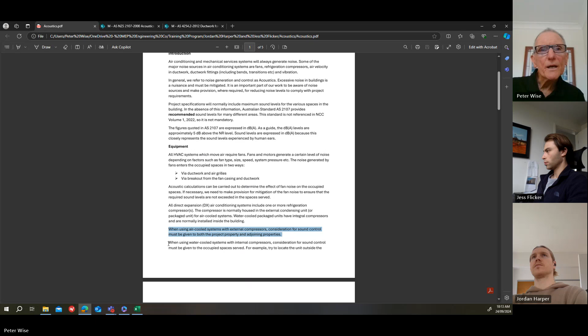When we're using water-cooled systems with internal compressors, consideration for sound control must be given to the occupied spaces served, as I was just saying. Try to locate these water-cooled package units outside the space served. So put them in an adjacent room which is not occupied. For instance, if it's a school, they used to be quite popular for schools and university buildings. Try and put them into an adjacent space that's not normally occupied, and then put some attenuation in the ductwork, internal lining.